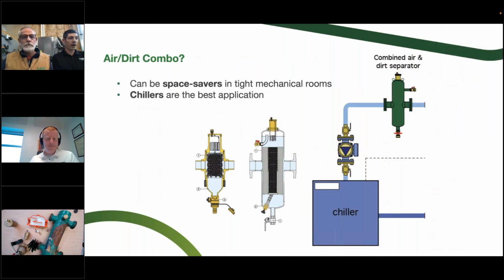For sure. So what about a combined device? The short answer, we could spend 10 minutes on the slide or 10 seconds: use them for chillers. There are some cases where it helps space-wise, if you're limited, to have an air separator and a dirt separator combo on a heating system. Ideally, we want to split those. We want the air separator in the hottest spot, and the dirt separator in the dirtiest spot. That is the same spot for a chiller system, because your warm return is going to be the dirty fluid from the distribution. So that's where we would use a combined air and dirt separator combo like that.